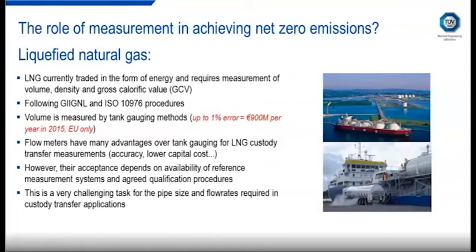So at the moment, LNG is traded in the form of energy, which means you have to measure the volume, the density, and the calorific value to get an overall energy value for the fluid. The standards that are followed come from the GIIGNL and the ISO 10976 procedures. At the moment, the volume measurement is typically done by tank gauging methods, and there's quite a high financial exposure associated with measurement uncertainty. So within the EU alone, a measurement error of 1% corresponds to nearly €1 billion per year.